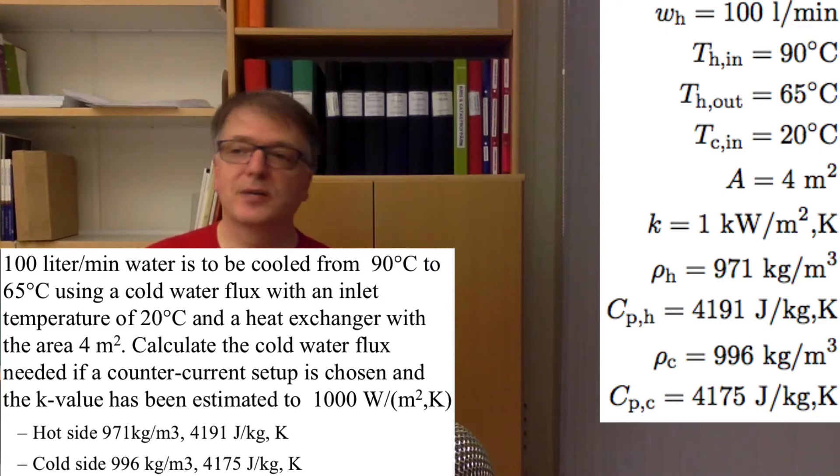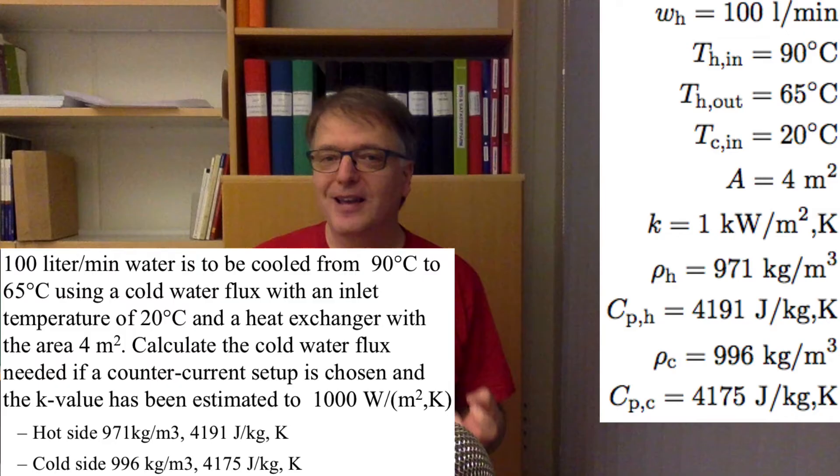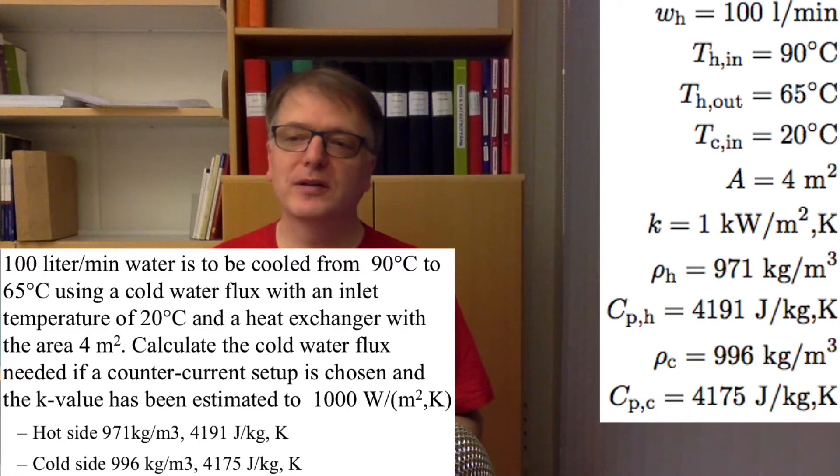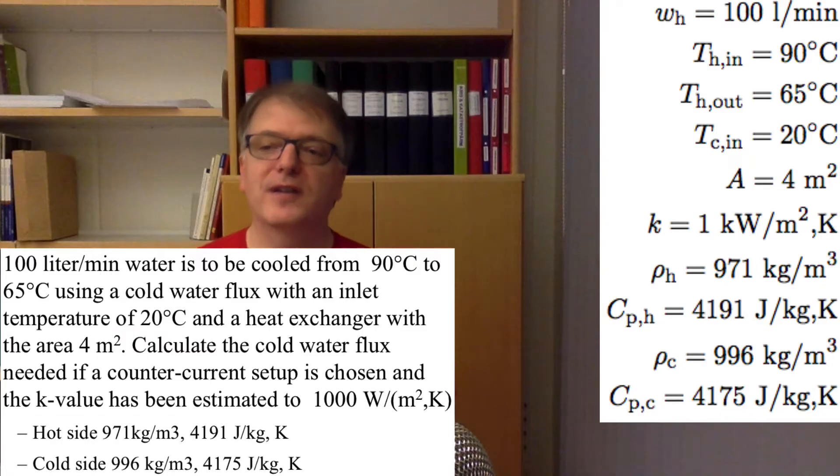On the hot side we have 971 kg/m³ and 4191 J/(kg·K) as the heat capacity. On the cold side, well we actually don't know the temperature so you can't look that up, but let's assume that it's 996 kg/m³ density and 4175 as the heat capacity.